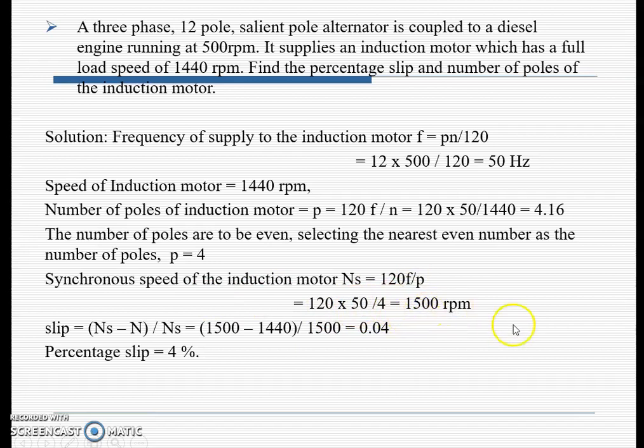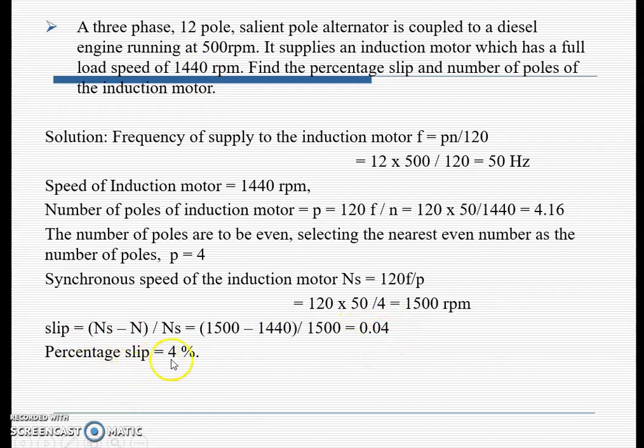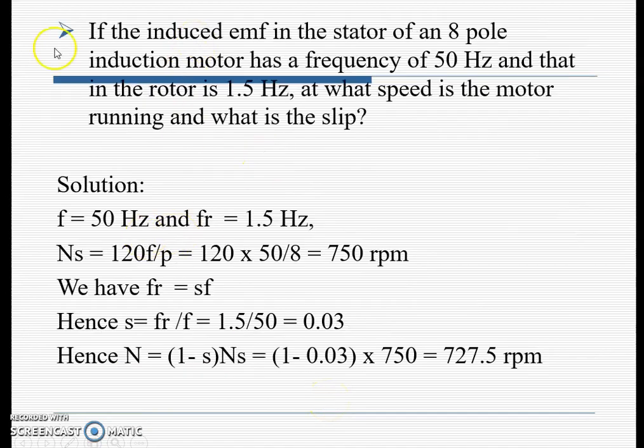The slip is calculated as s = (n_s − n) / n_s = (1500 − 1440) / 1500 = 0.04, which is 4%.